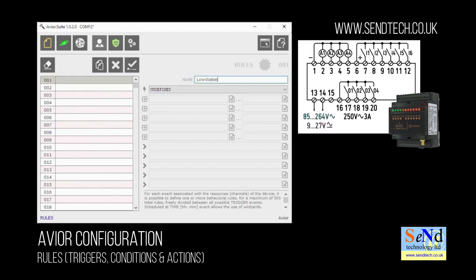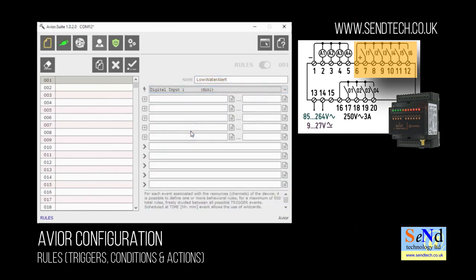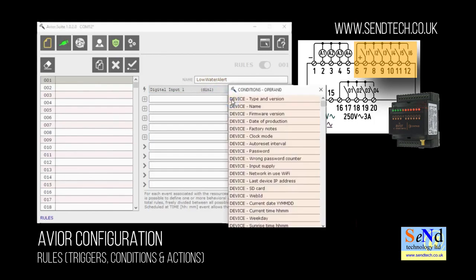First of all let's give it a name. In this example we'll call it low water alert and we'll be using a float switch as an input to measure the water level. That's a digital input so we'll define the trigger as a digital input, and digital input 1 as shown in the wiring diagram to the right.